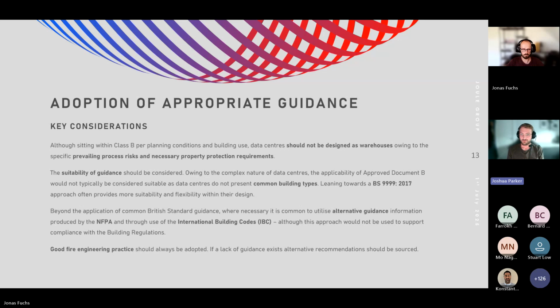So when we look to adopt appropriate guidance, as we mentioned, data centers shouldn't be designed as warehouses, so applying guidance for those particular buildings really shouldn't be adopted. We need to provide more of a granular assessment of the prevailing risks within that building, and what those risks present. How can we best overcome those risks, and what guidance would allow us to do that? The suitability of guidance should be considered owing to the complex nature of these buildings. So leaning more towards a risk-based approach as presented in BS 9999 does enable that application of guidance in a best practice manner.